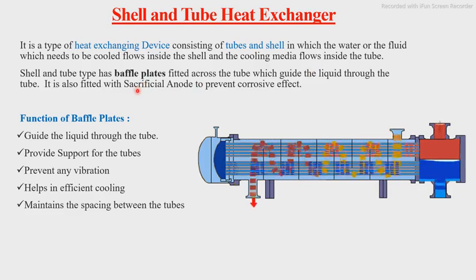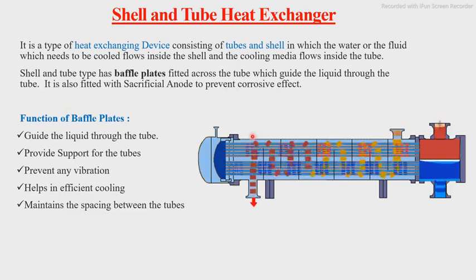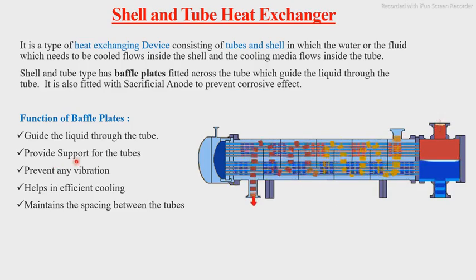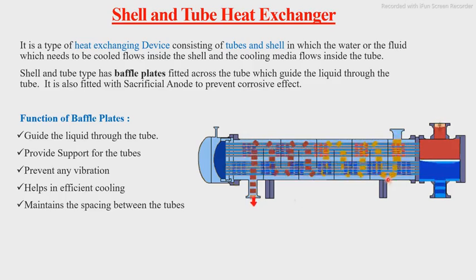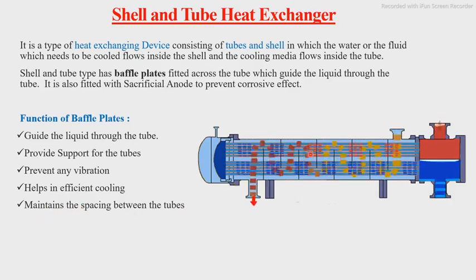The shell and tube type also has a baffle plate fitted across the tubes which guides the liquid through the tube. It is also fitted with a sacrificial anode to prevent corrosive effects. The functions of baffle plates — commonly asked in interviews and exams — are: they guide the liquid through the tube; they provide support for the tubes; they prevent vibration; they help in efficient cooling by increasing the surface area in contact with the tubes; and they maintain the spacing between the tubes.